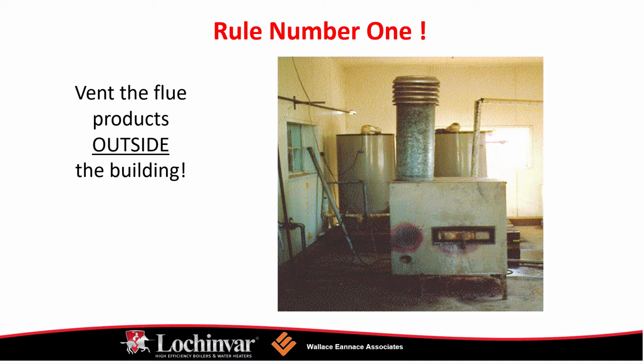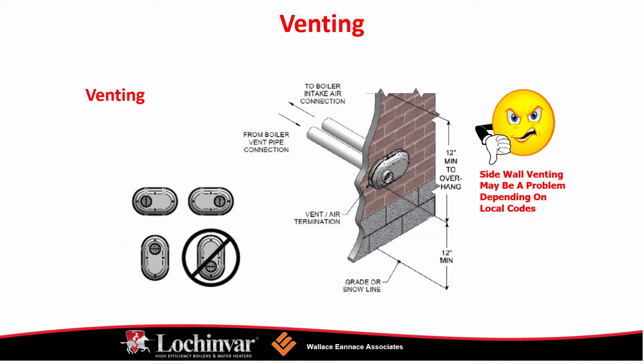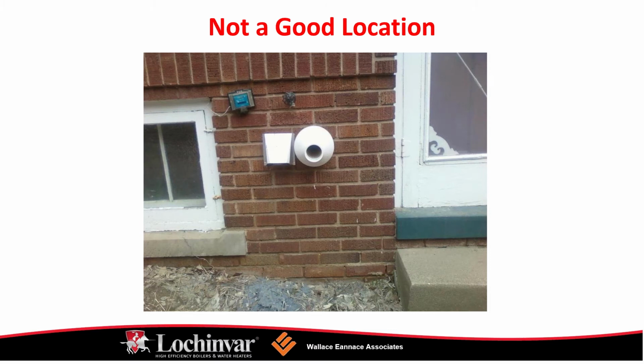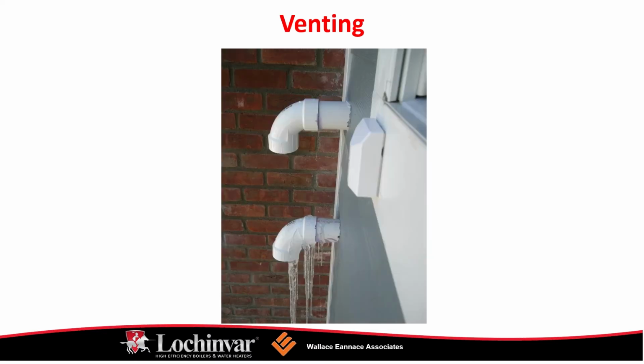Venting. So, venting and approved materials. This is pretty neat because we do allow PVC and CPVC pipe. Of course, that can be an issue in certain municipalities, as most of us know, certainly including New York City. Stainless steel, AL294C rigid pipe, AL294C flexible pipe, polypropylene, which must be approved first, and don't use foam core.